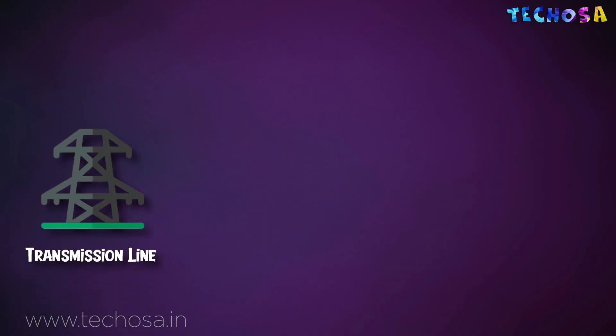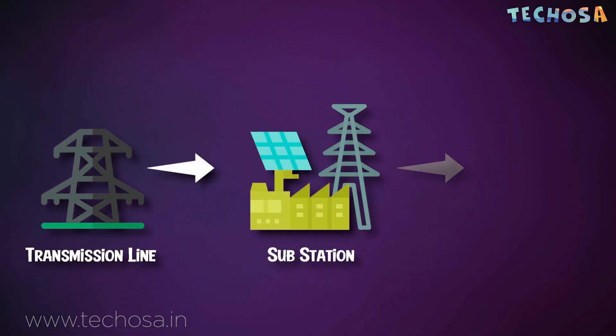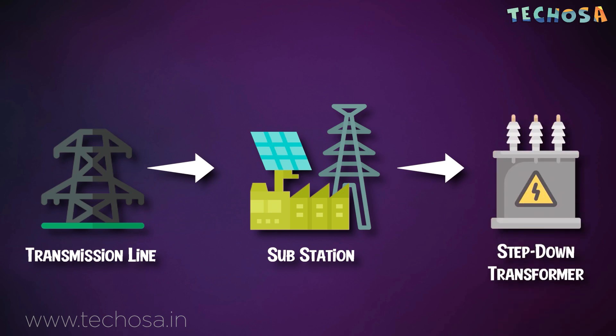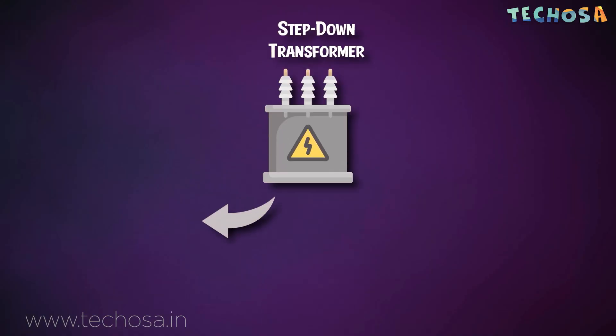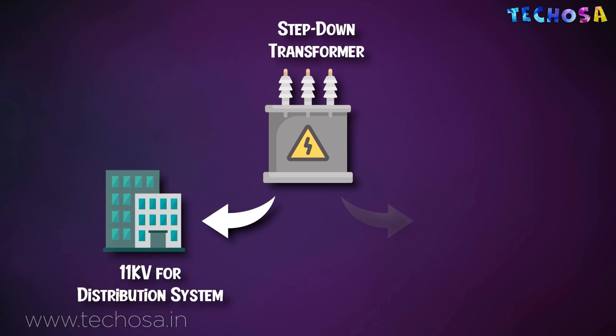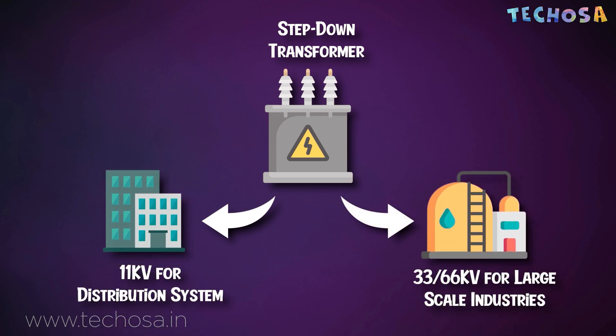Higher voltage means that less heat will be generated during transmission through the wires. From the transmission line, the electricity reaches the substation where the voltage is reduced using a step-down transformer. A step-down transformer is used to reduce voltage; as voltage decreases, current increases. The voltage is reduced in two stages: 11 kV for the distribution system that reaches our homes, and 33 or 66 kV for large-scale industries.